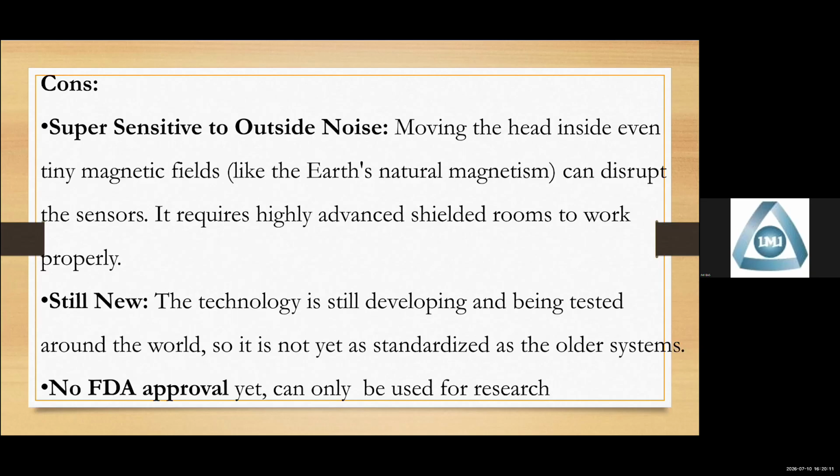It's super sensitive to outside noise. Moving the head inside, even a tiny magnetic field like the Earth's natural magnetism, can disrupt the sensors. It requires a highly advanced shielded room to work properly.